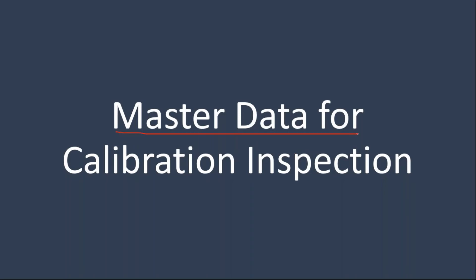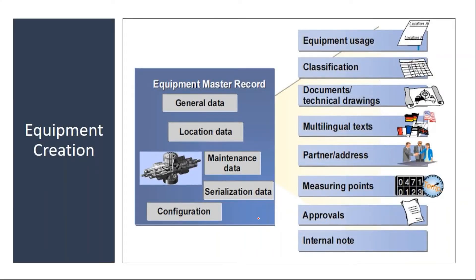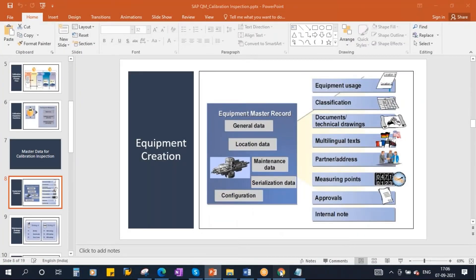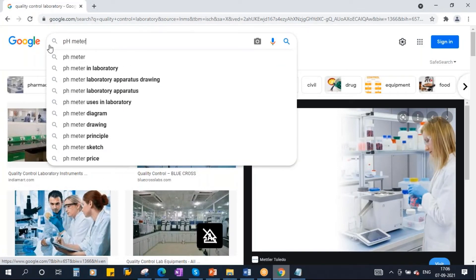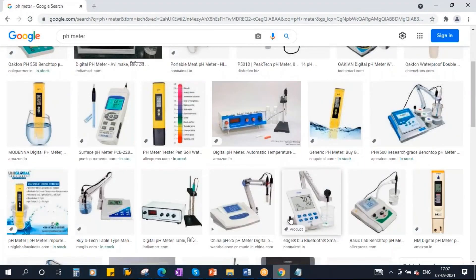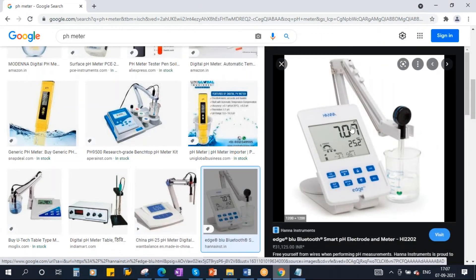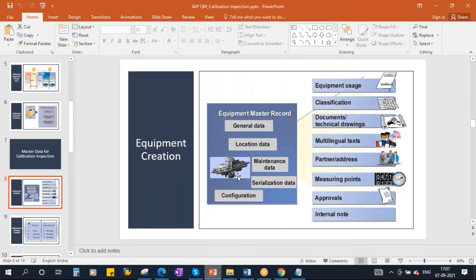Now we will talk about the master data required for calibration inspection. First, you need to create equipment — every test equipment in the quality lab is created as an equipment record. For example, to check the pH value in the lab they normally use a pH meter. I will create this pH meter as an equipment record. If I want to calibrate this pH meter once a month, first I need to create it as equipment in the system. This will be done by the Plant Maintenance team in real time.